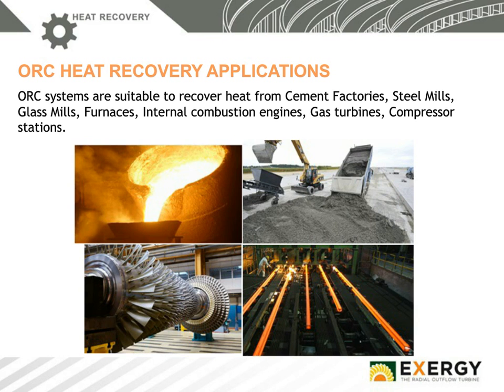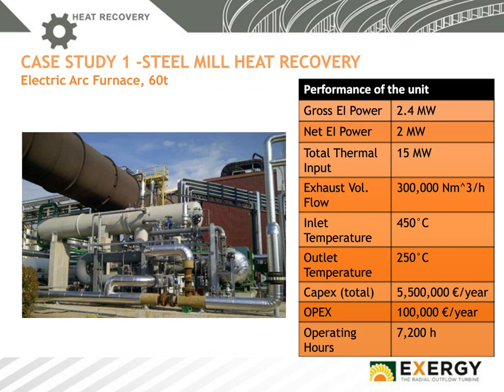The application of the ORC in heat recovery, as Anthony has already anticipated, can be in many different industries. So we can say cement, steel mills, glass mills, furnaces, and also power generation like gas turbines or engines and compressor stations. We will start with a steel mill case. This is the case of a quite small steel mill, approximately 60 tons of steel per cycle, and what results from the heat recovery is 2 megawatts of net electrical power.